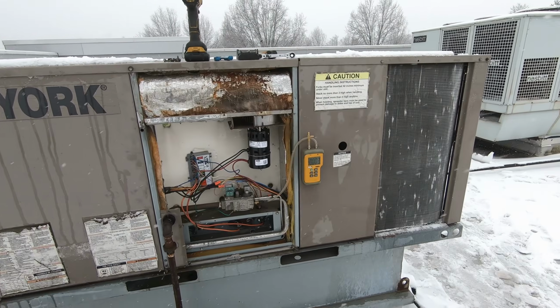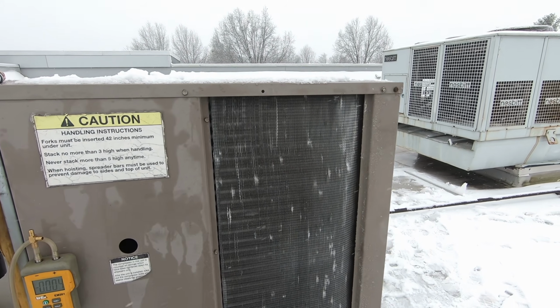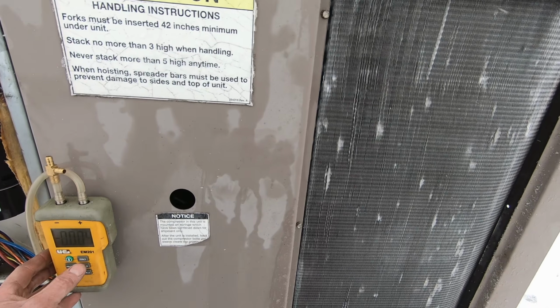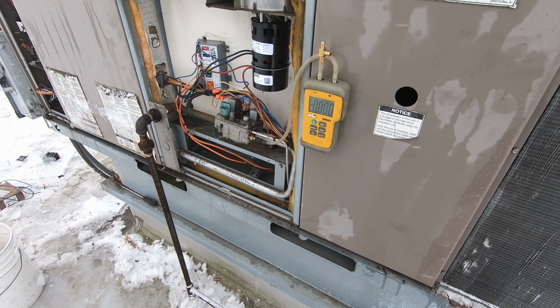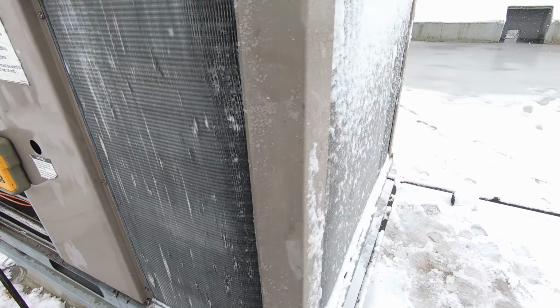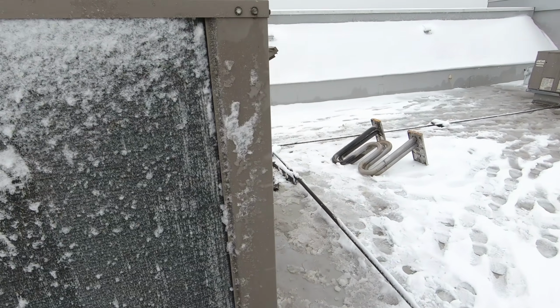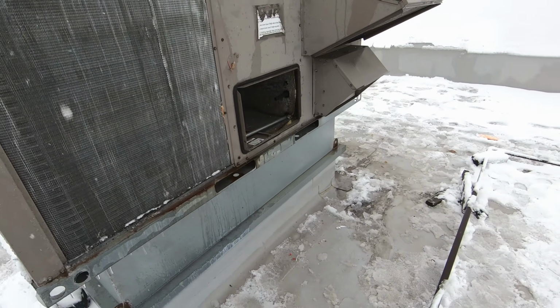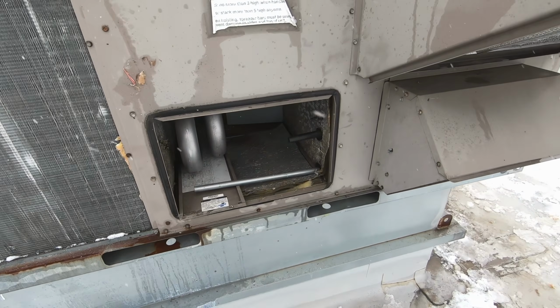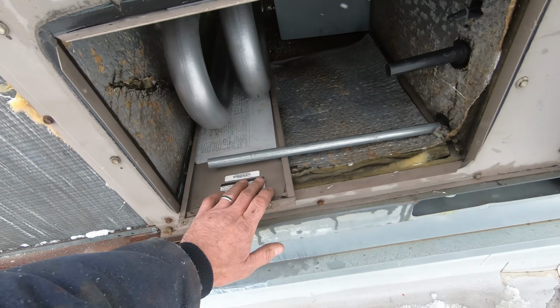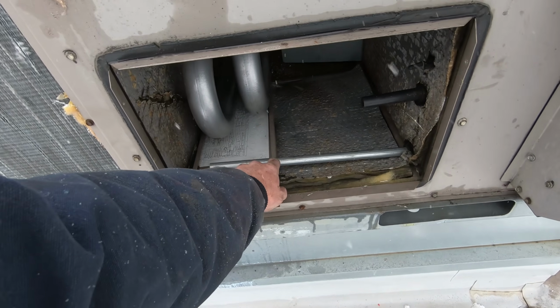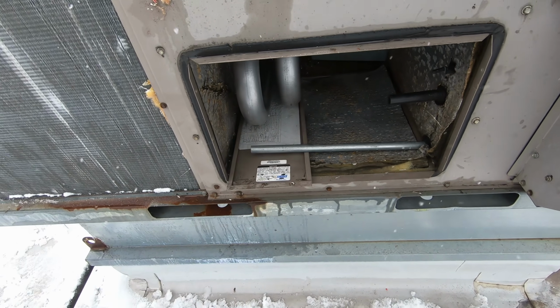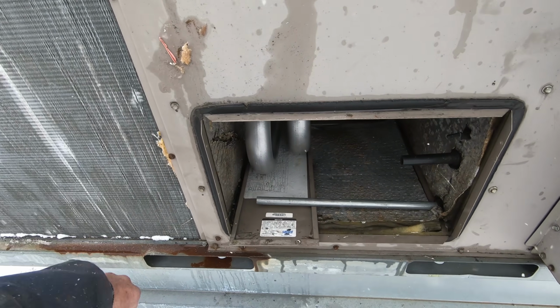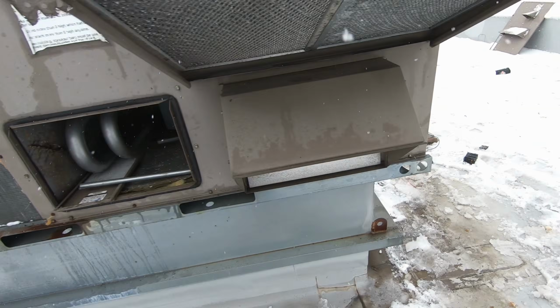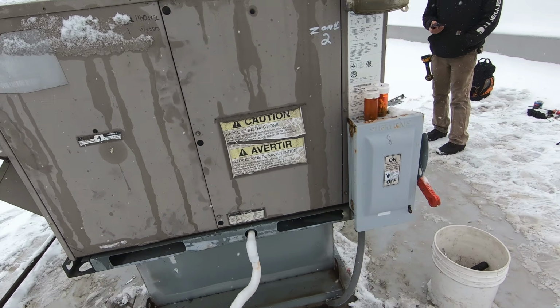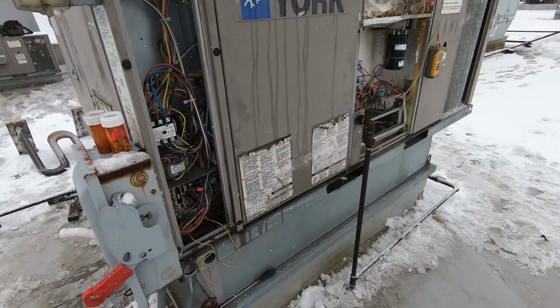We got all the panels back on, got the lid, and the condenser fan motor in place and wired up. I've got my manometer hooked up to the gas valve. I let them know we were about to fire it up. They got the fire suppression system and fire alarm put in test. I used a couple of the panels here to block off the supply duct, but as you can see, we've got a smoke detector tube right here, so I wanted to make sure they had this system in test. Other than that, we're good to fire this thing up.